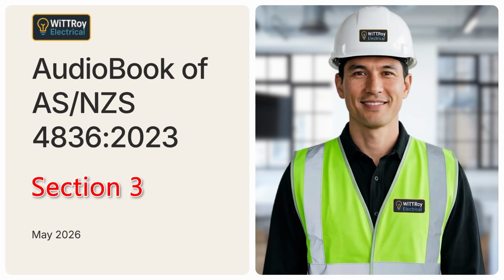There is also an important warning about the MEN connection. MEN means multiple earthed neutral. If a neutral earth connection or MEN connection has been removed, it must be reinstated. In New Zealand, the electricity supply industry also uses voluntary rules and guidance from the Electricity Engineers Association of New Zealand. The message is this: fault finding is not casual testing. It must be planned, assessed, controlled, and carried out by competent people using suitable test equipment and safe work methods.